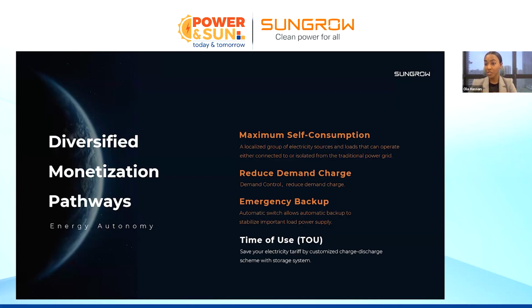So number one, which is the most common in the GCC area, when we have stable grids, sometimes we want to maximize our self-consumption. Maximizing the self-consumption means that the grid is stable. However, I want to increase my reliance on my PV system. I want to reduce my reliance on the grid. I want to reduce my electricity bills. So this is what we call maximizing the self-consumption, where the priority will be for the PV system. Then the second priority is to discharge my battery to support my load. And when the battery is fully discharged, then I rely on the grid. So our concept here: the grid is stable, but we are reducing our reliance and dependence on the electricity grid. We are reducing our electrical consumption and bills, and we are relying more on our PV system and battery.